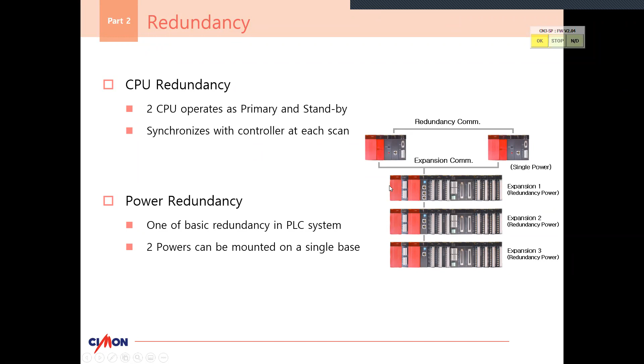When we talk about CPU redundancy, this is 2 CPUs side by side, one that takes over in case the other fails. Some call this master and slave, others primary and secondary - whatever term you've heard, this is CPU redundancy in general. If one fails, the other takes over, and they're both communicating synchronously, talking to the IO cards. Down here, we see power redundancy as well for the IO cards - a typical setup for redundancy in general. There are 2 power supplies, and a module in the middle monitoring both to make sure they're operating properly.